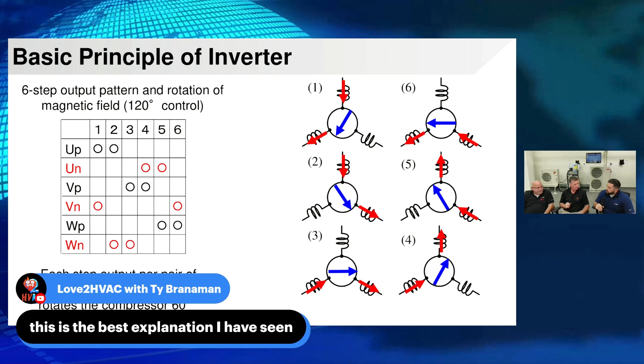We could be anywhere from 30 hertz all the way up to, with some of our hyperheats, up to 127 hertz. So we're talking overdriving, overramping - really fast, and that's how we drive that compressor. That's how we're able to get those low ambient temperatures and still be able to make heat, because we can overdrive those compressors really hard. If we only have 60 hertz coming in, that's all we can drive. But now that we start looking at going past that total frequency and speeding them up a little faster, that means we get more capacity out of that compressor.